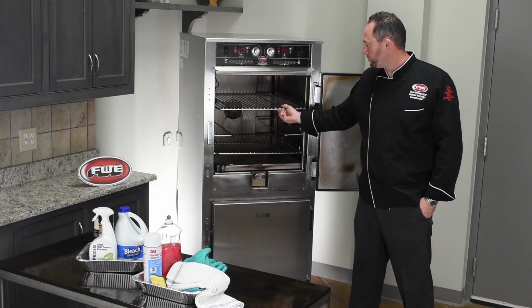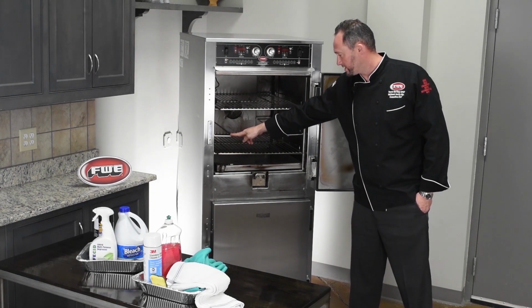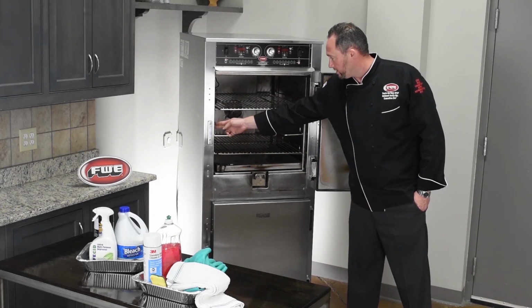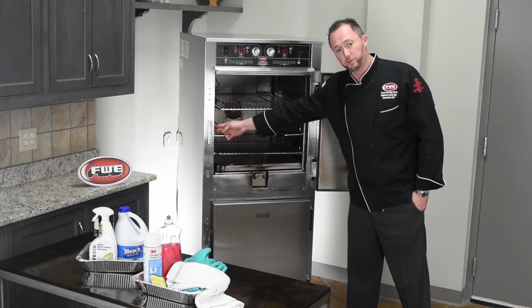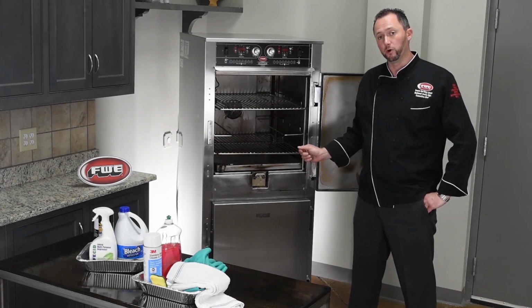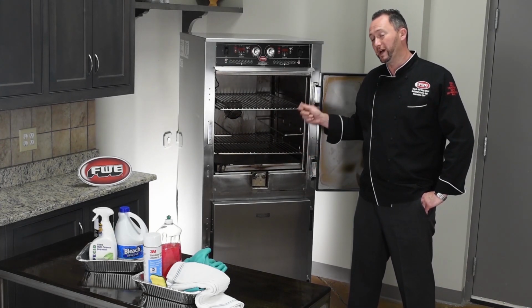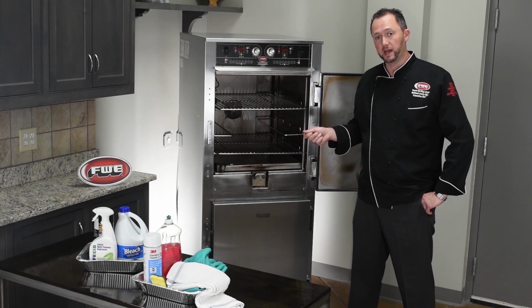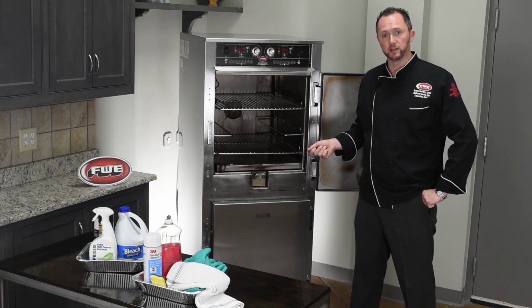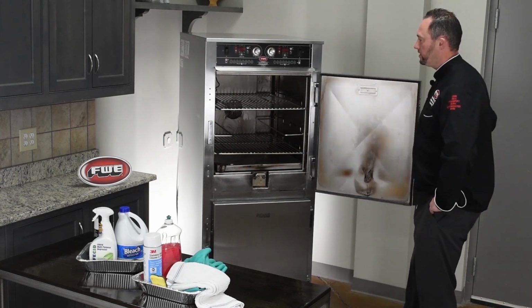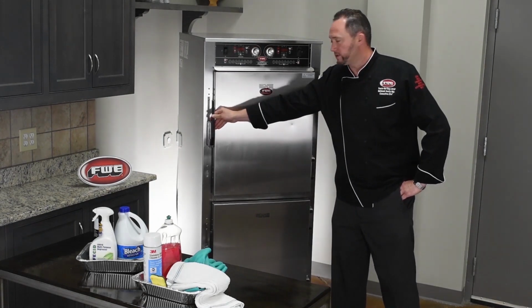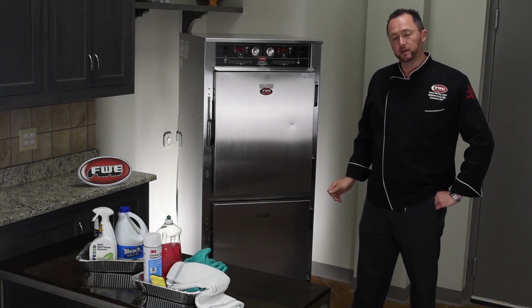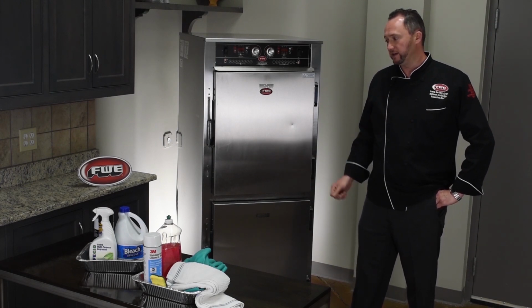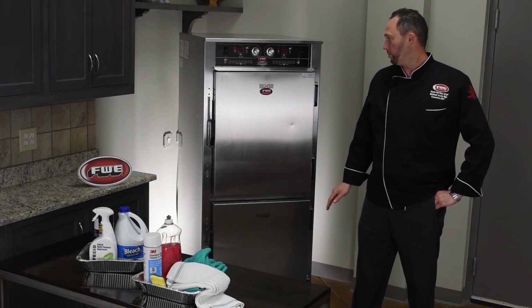The rack slides are removable, as well as the adjustable tray slides as we covered earlier. The probe may also be removed. One thing to be cautious with the probe, make sure that when you do clean the probe, do not leave it submerged in water. Wipe it down with a sanitizing solution and let it dry before reinserting into the unit. On the outside of your unit, you may use that same soap and water solution to clean, or if you prefer a factory shine, using some stainless steel cleaner will make that happen.